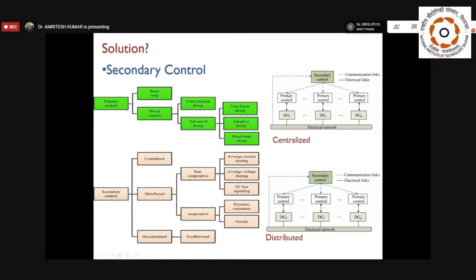Okay, so we require another controller that gives the command to boost the reference voltage so that we can reach the reference value. Basically this secondary control will compare the voltage to the reference voltage, like suppose 250 volt. It will compare it with the actual voltage you are getting, and the error is going to be passed, based on the controller output, to all the primary controllers. So whatever information the secondary control is giving goes to all primary control.